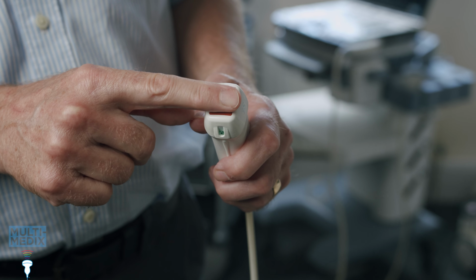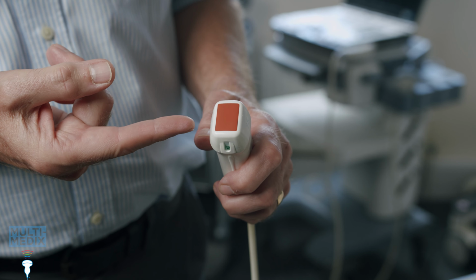This is a fairly simple test, but setup is important as clinical settings can mask faults. We're going to use the paperclip test to look at uniformity, so we need the lens to be clean and dry with no gel. But for some probes, you might want to wet the lens with a little bit of water to make the paperclip run smoothly. At baseline testing, a preset for user QA will have been set up, so that makes it easy this time round. Just select the preset and check all the settings.